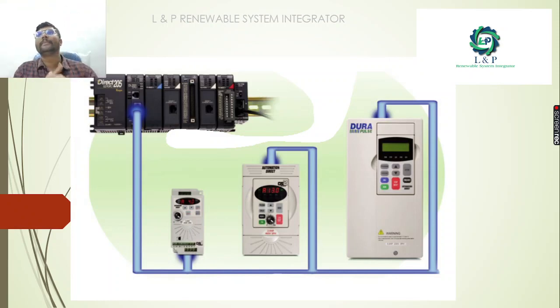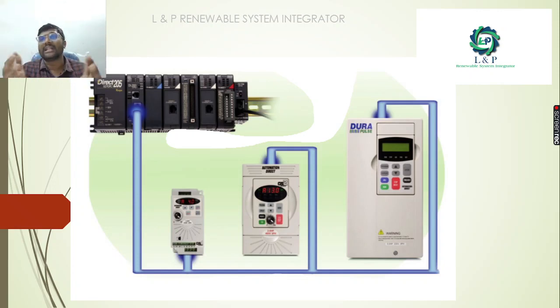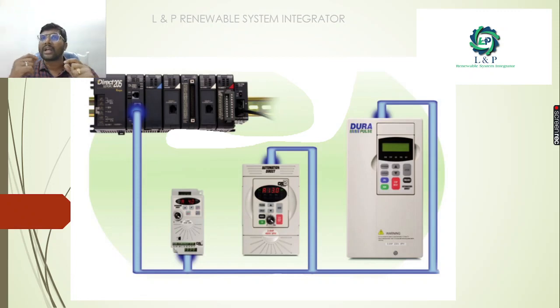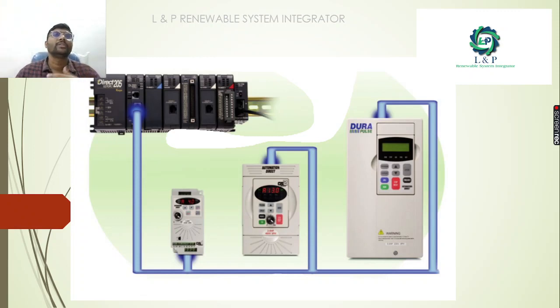As we know, variable frequency drives especially need a separate power supply for their running. Apart from that, it has two features: the controlling feature and the monitoring feature. The monitoring is done through feedback. For controlling and monitoring, we can use either current or voltage. Current can be from 4 to 20 milliamps; voltage can be from 2 to 10 volts. Similarly, for the feedback signal, either as current we can take 4 to 20 milliamps, or sometimes as voltage 0 to 10 volts.